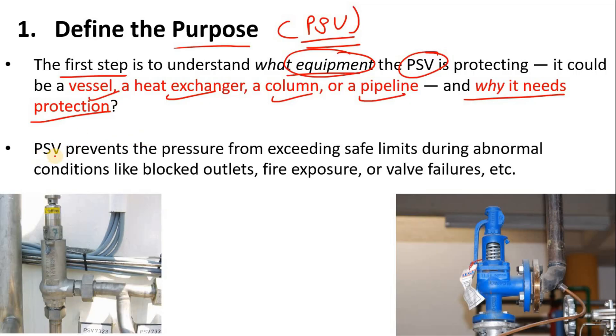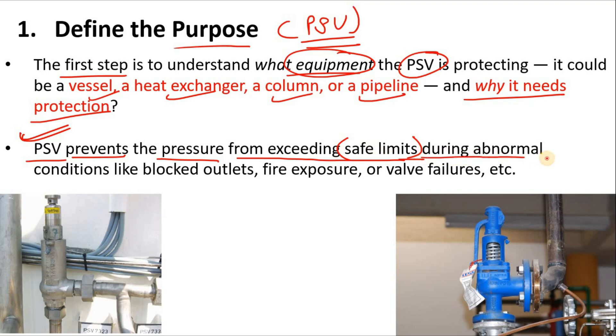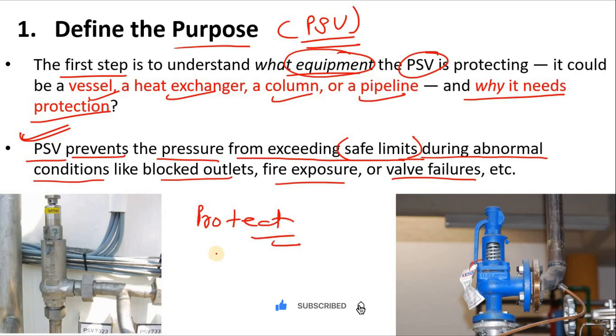The role of the PSV — pressure safety valve or relief valve — is to prevent the system from over-pressurization. It protects your vessel, heat exchanger, pump, column, etc. The PSV prevents pressure from exceeding the safe limit during abnormal conditions. Abnormal conditions could be blocked outlet, fire exposure, or valve failures, which we will discuss in further slides.